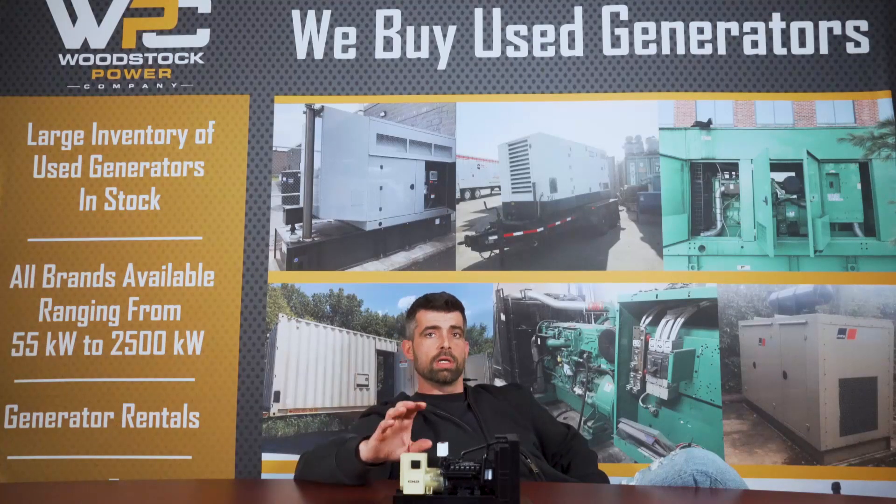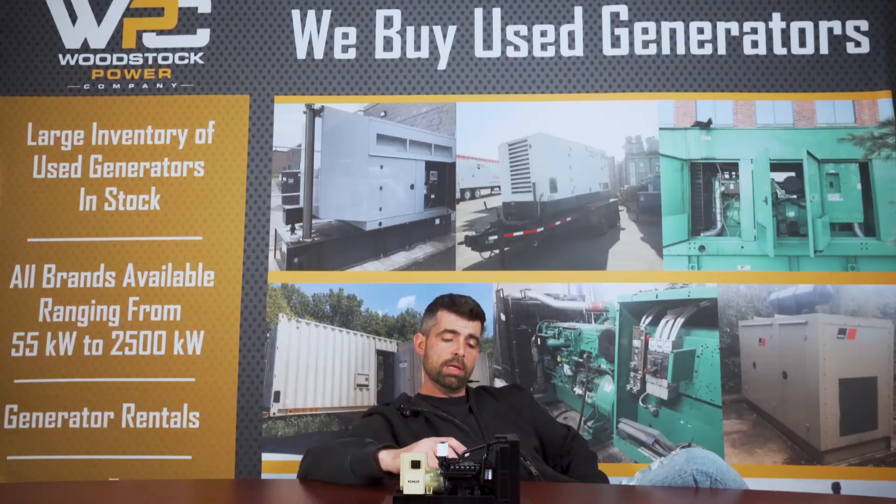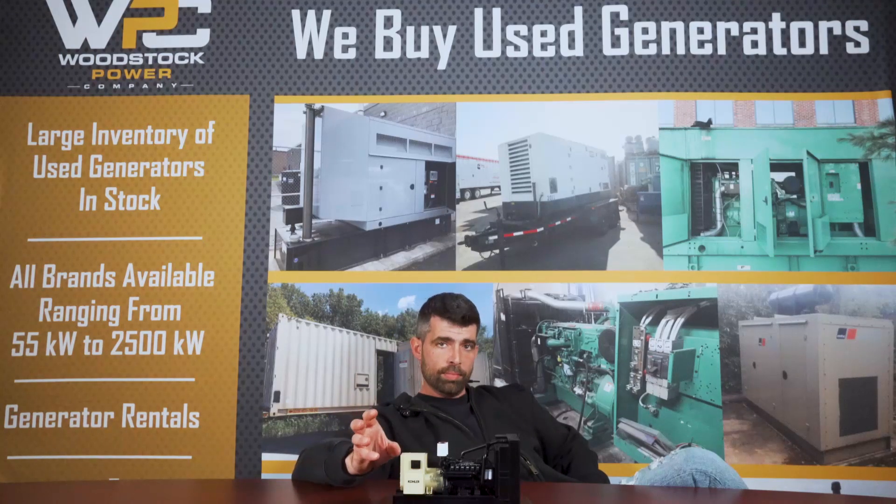First, as mentioned, running your engine at less than its prime rated capacity — less than 80% of its rated plate. A second reason is if you haven't used your generator for a long time. It was sitting outside or inside and cured some moisture inside. When you go to turn it on, you might notice it sputters a little bit or there's extra smoke coming out. You might get a derate mode or a derate fault as a result.